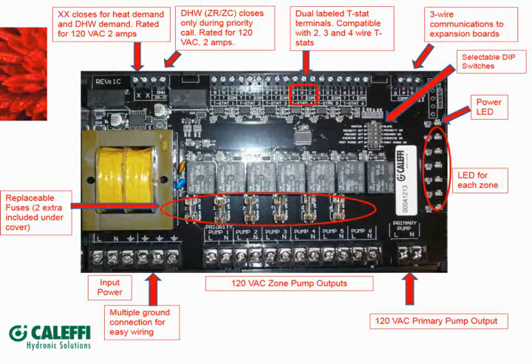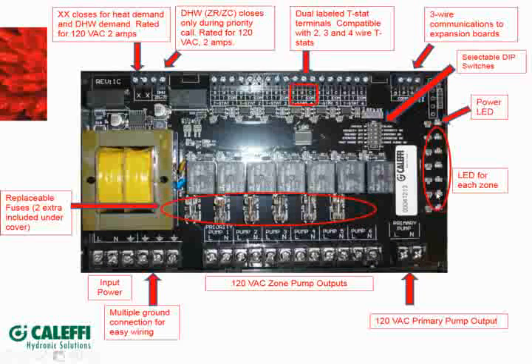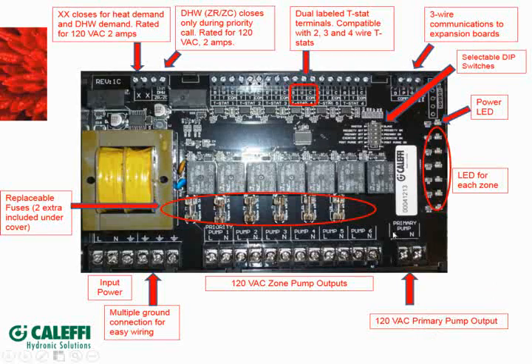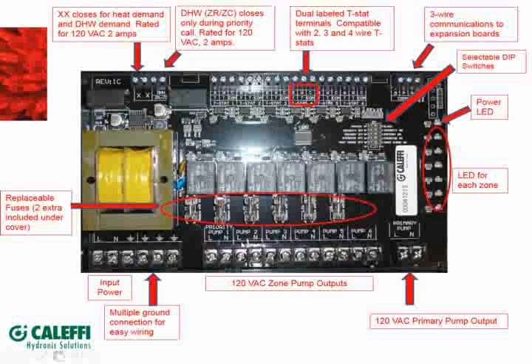Yep. So over here, the power LED and then the LED for each zone. So when there's a call, these LEDs will light up. We have a primary pump output down here, and like I mentioned before, we are giving you line and neutral, not just a switch. And then there's a priority pump. Zone 1 is always our priority zone if it's enabled. Line and neutral to all of these.